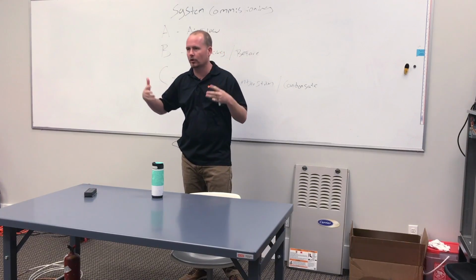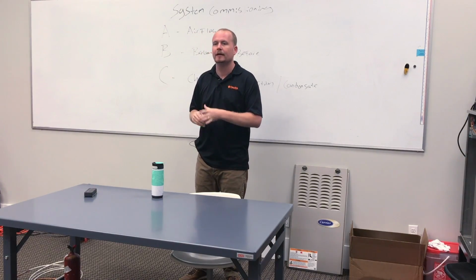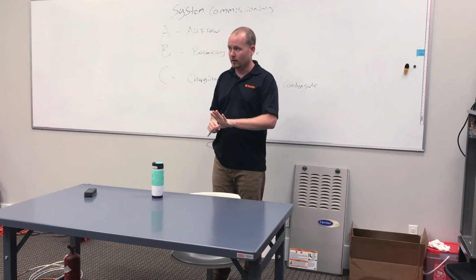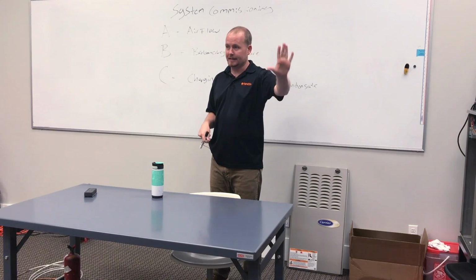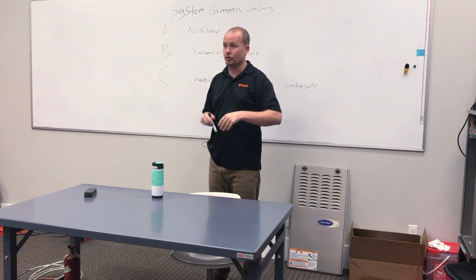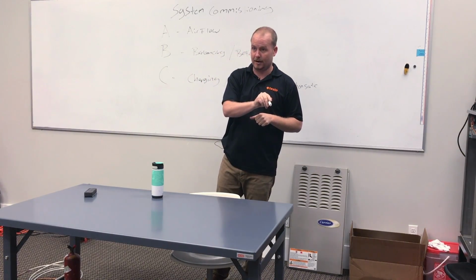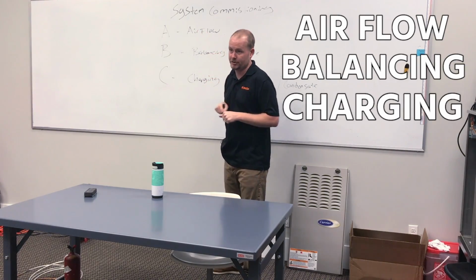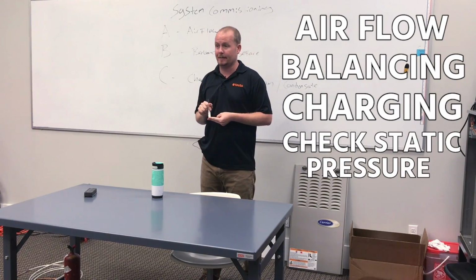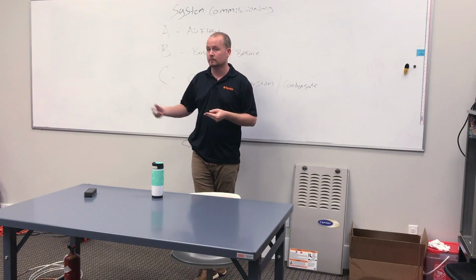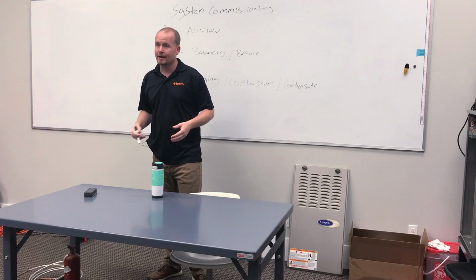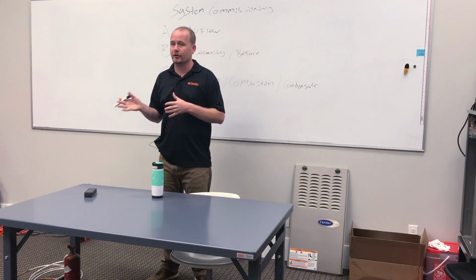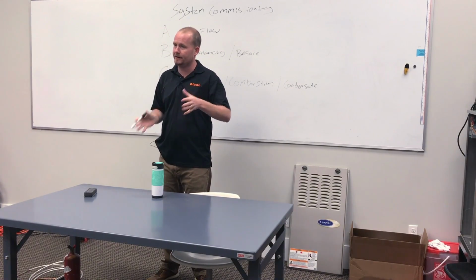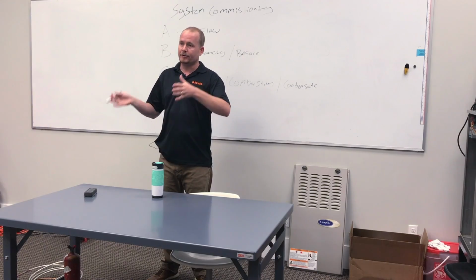I'm not going to go into all those specifics. Now we're talking about duct design. But do you get the point here? On an install, we have a blower that's supposed to produce a certain amount of CFM. You've got to set it up so it produces that, right? Again, airflow before charging. Then you've got to check your static pressure. Do those two things first. Do those two things while the system is ramping up, maybe 10 minutes into its running. Again, you want the coil to be wet before you start checking static pressure and things, because that will affect it. You don't want to do it on a dry coil. But do that first.